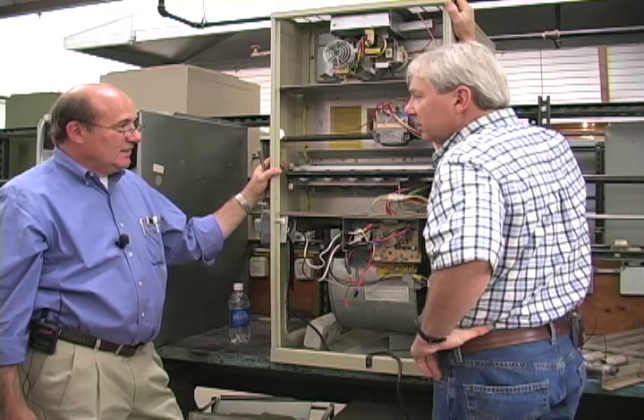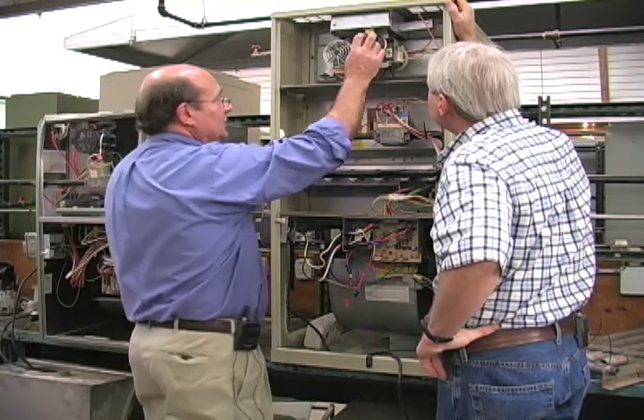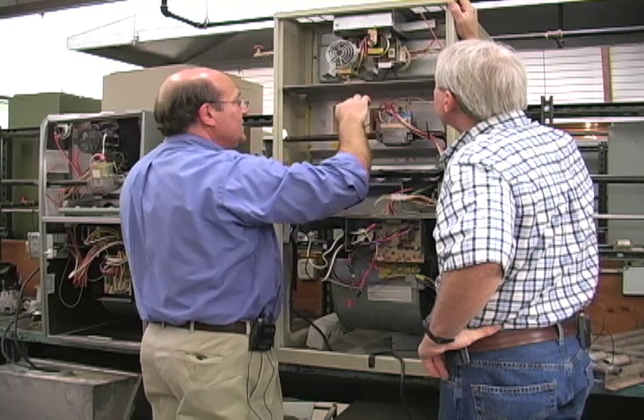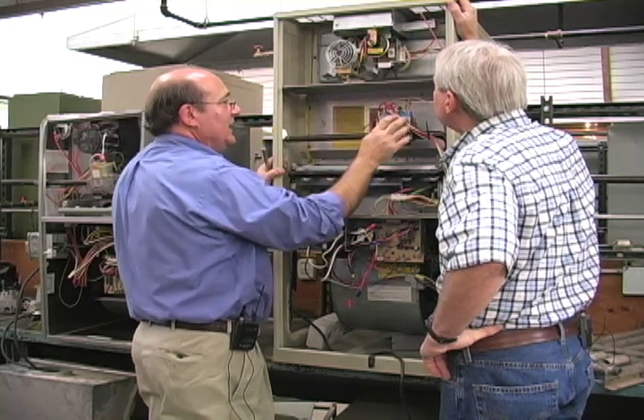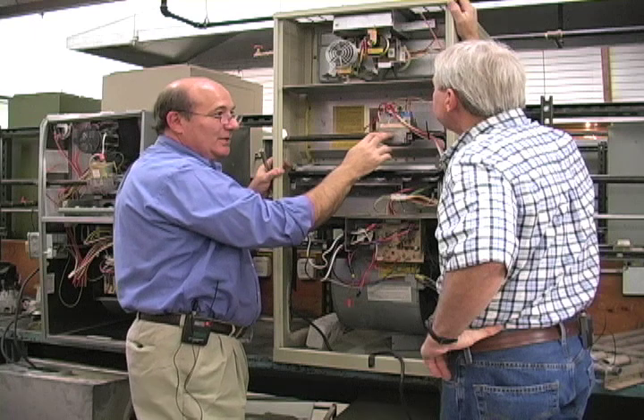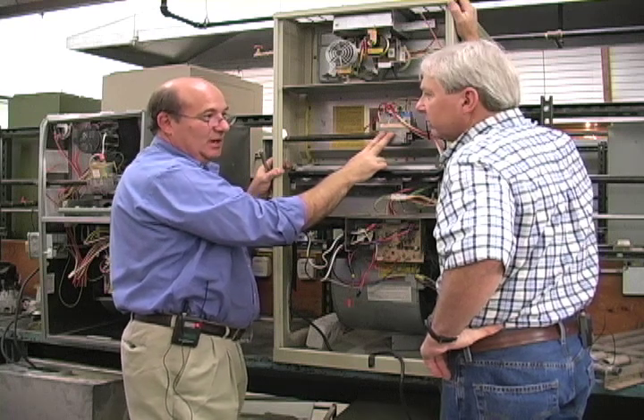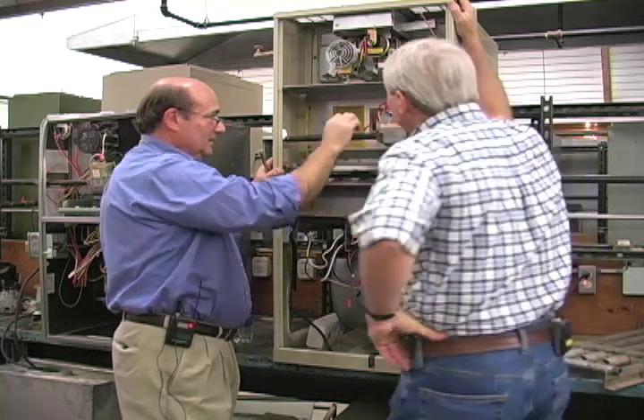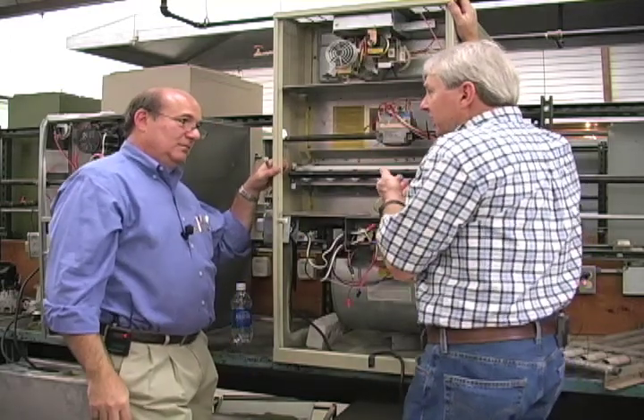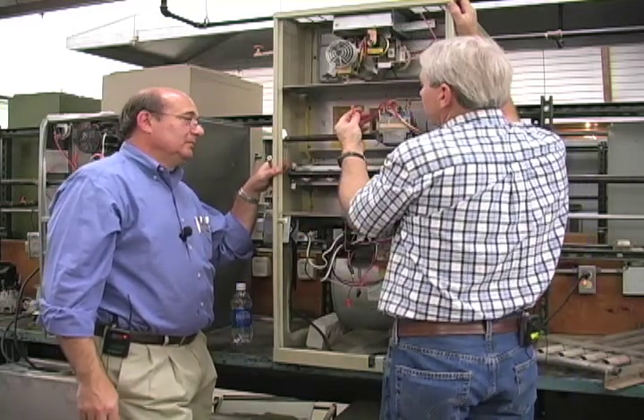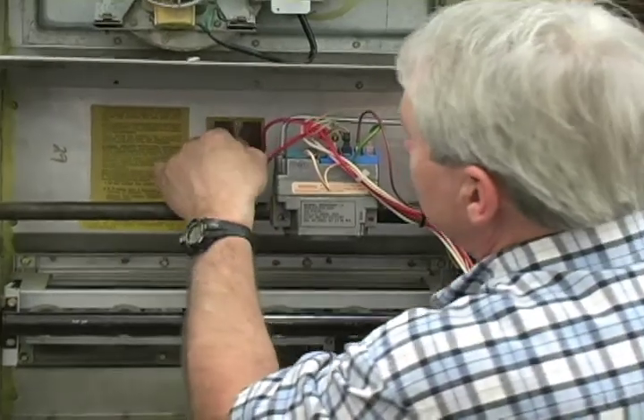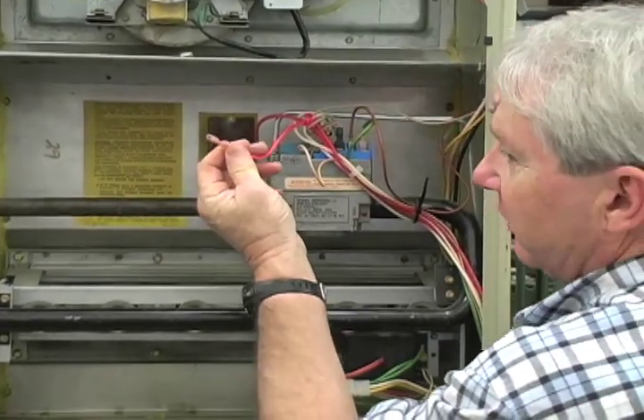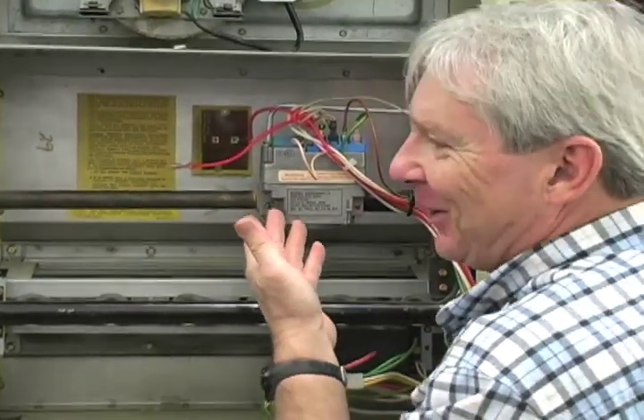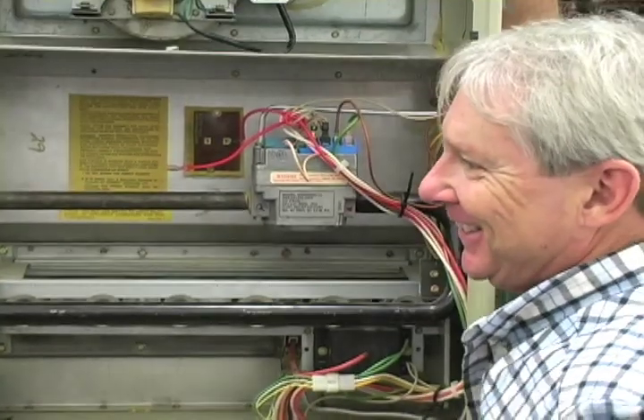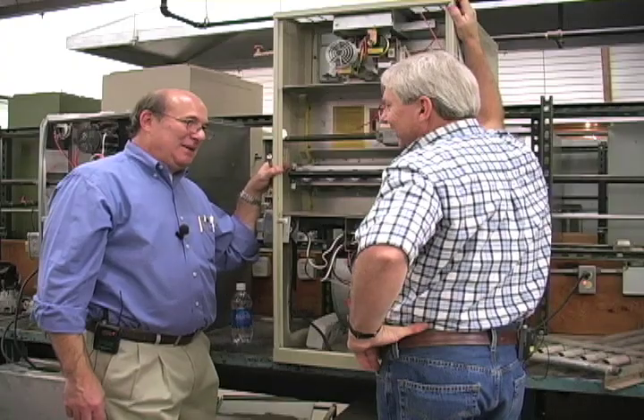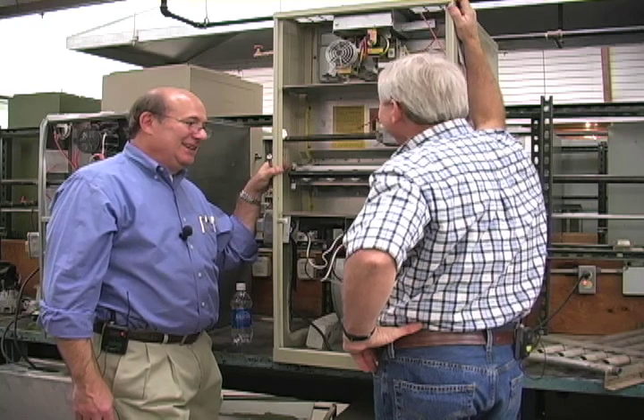If there's something wrong, a defect in either the combustion blower or any of these other switches, if for some reason that gas valve stays open, you've got a real problem with your gas valve. It's a serious safety problem. I'm wondering, the reason I can think of for an inspector not to do that is that if this is old and he pulls that off and the whole thing falls apart, they don't carry any tools for repairing furnaces. Well, I suspect that that's a hazard of the trade.